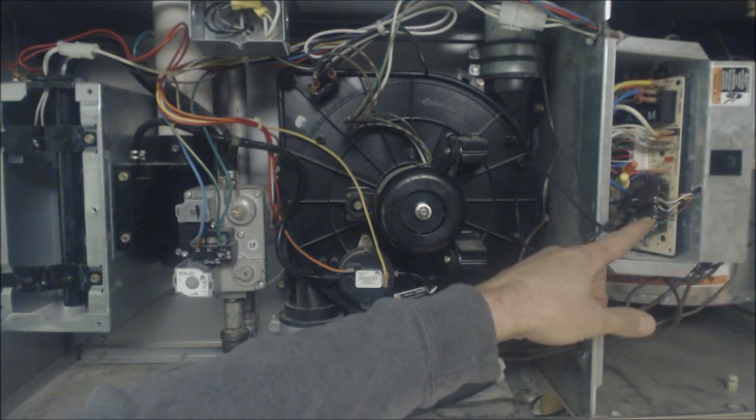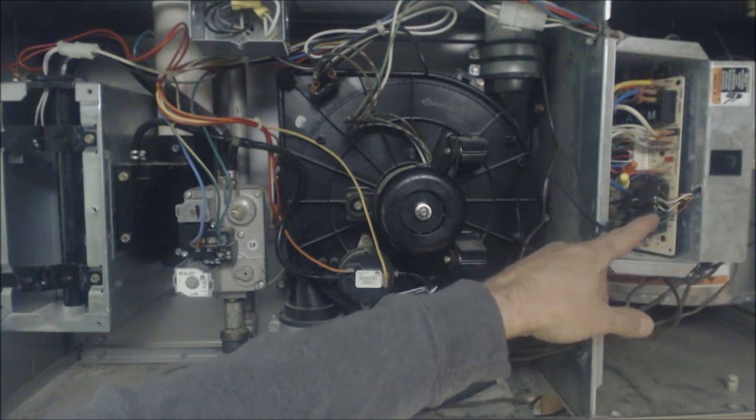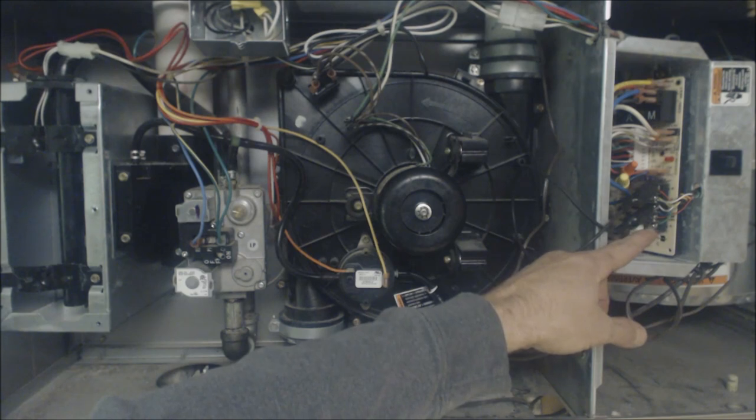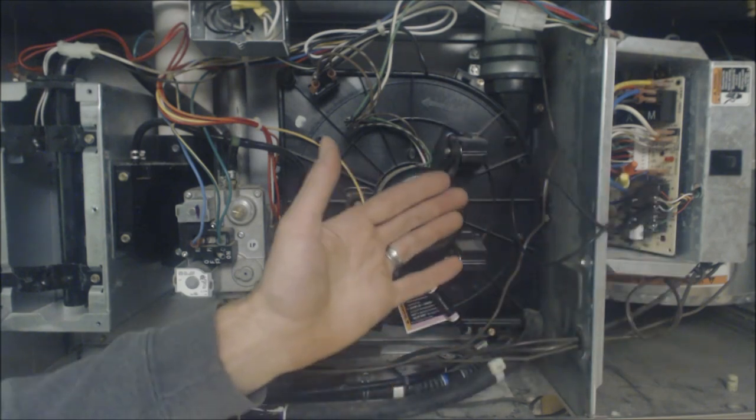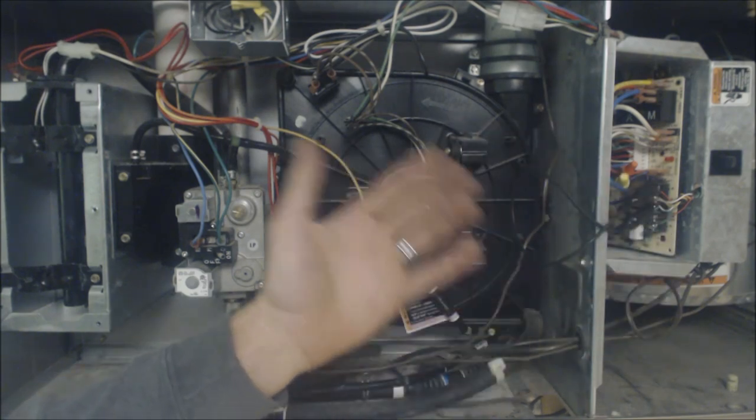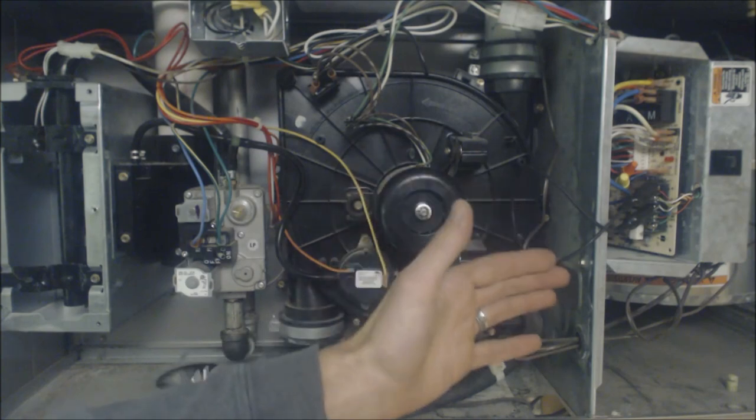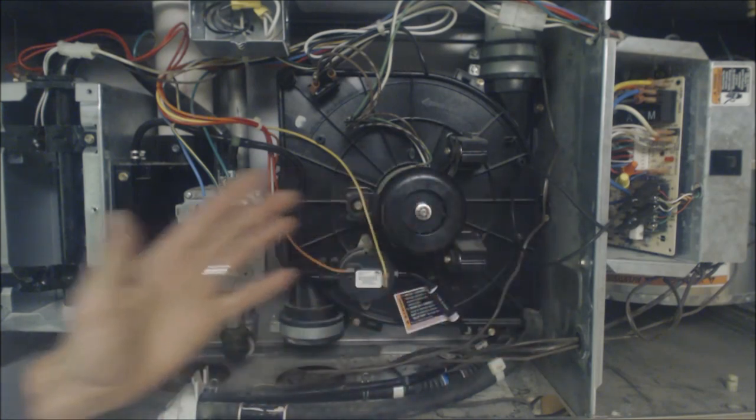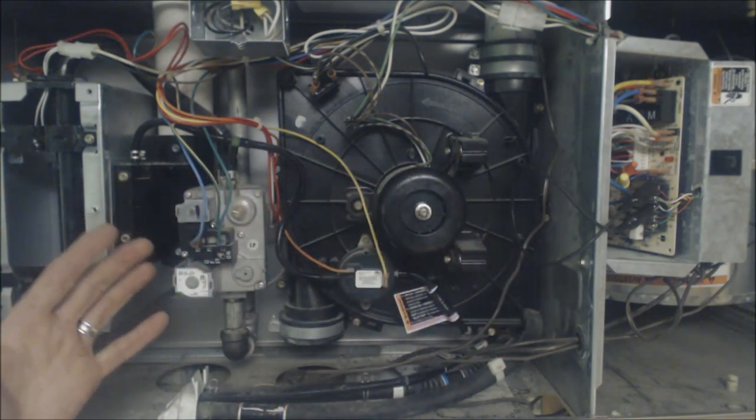If you want to take a voltage reading from W to C then you'll know that you have 24 volts to 28 and a half volts telling the sequence of operation of your furnace to go ahead and turn on.